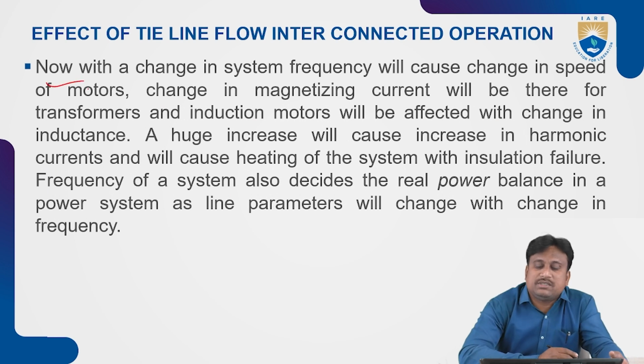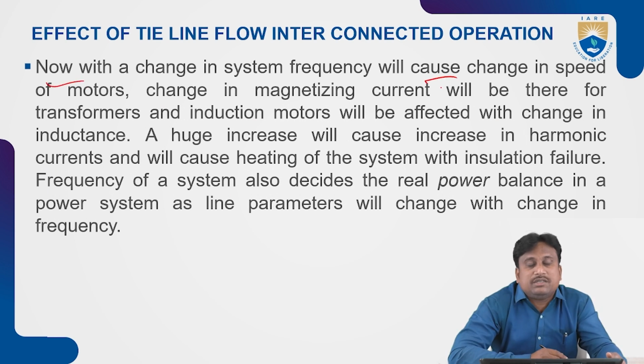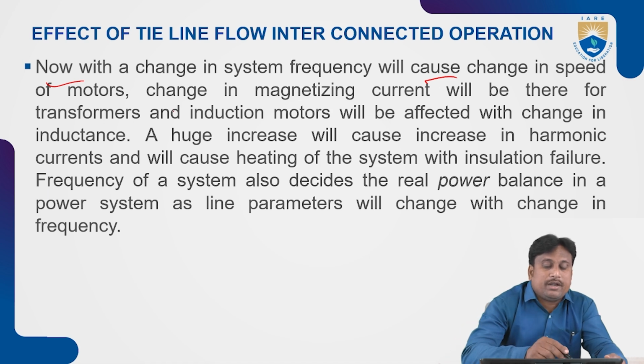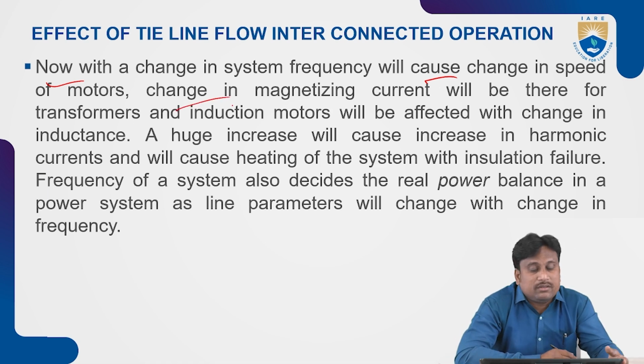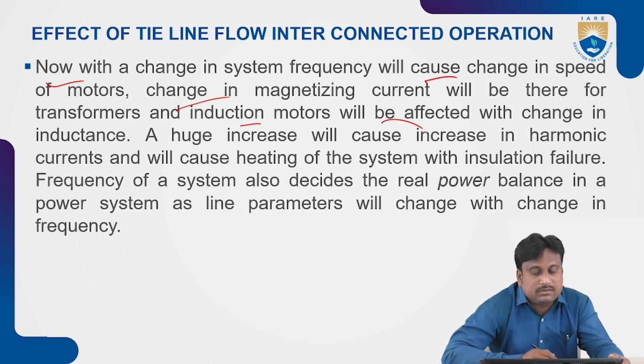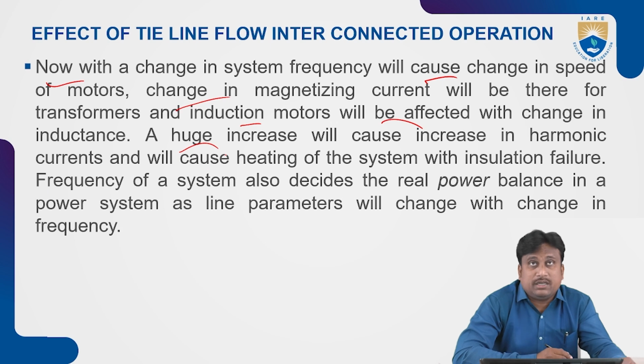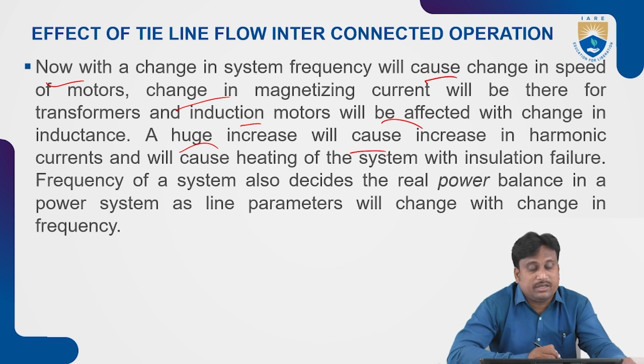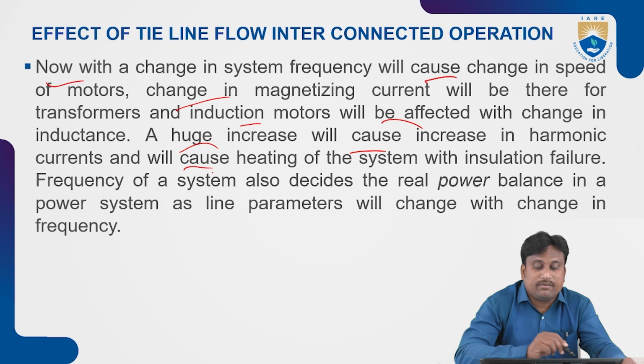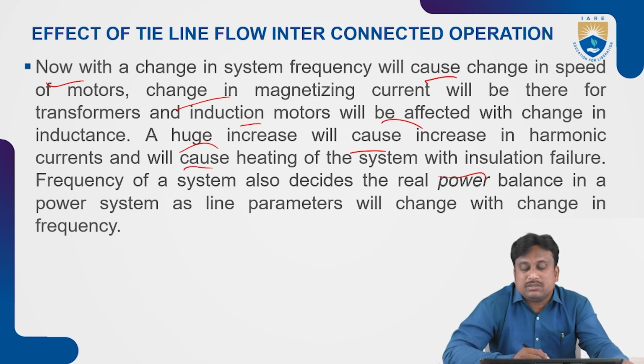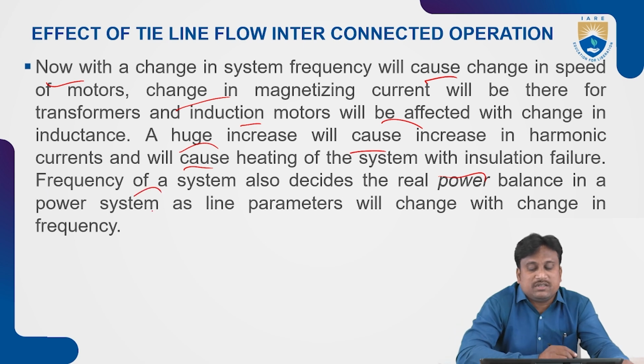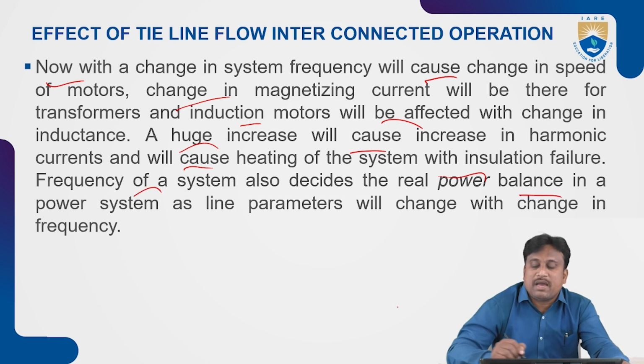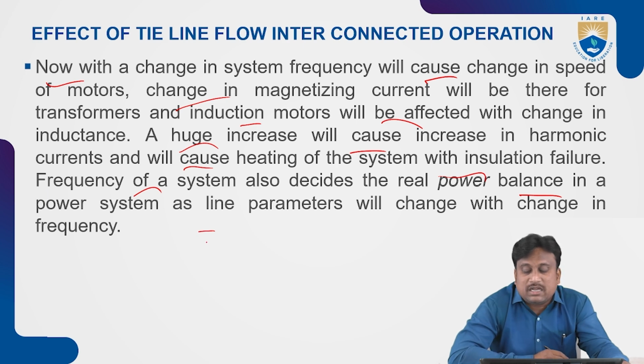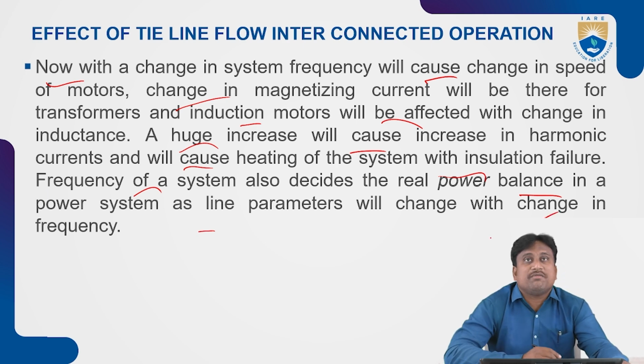Now, a change in system frequency may cause a change in the speed of the machines, which may change the magnetizing effect for transformers and induction motors, which will be affected by the change in inductance. So there may be a huge increase in harmonic currents, which will cause heating of the system. Insulation failure may also result, and the frequency of the system also decides the real power balance in the power system network, as the line parameters will change with changes in the frequency.